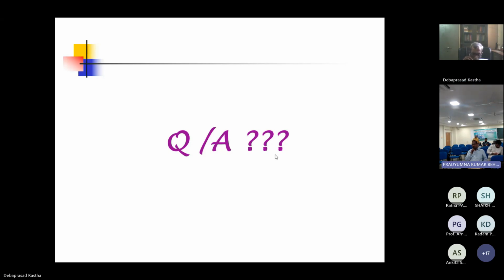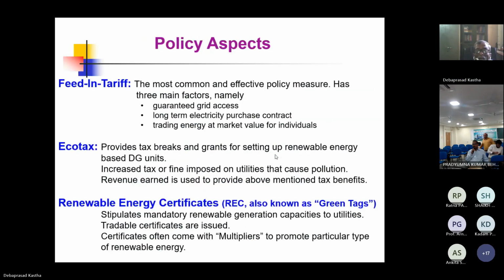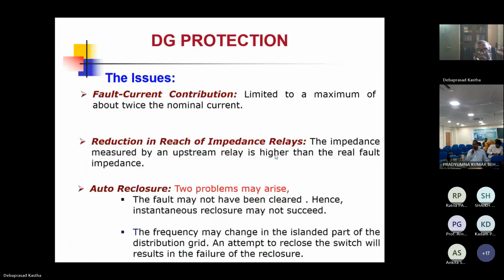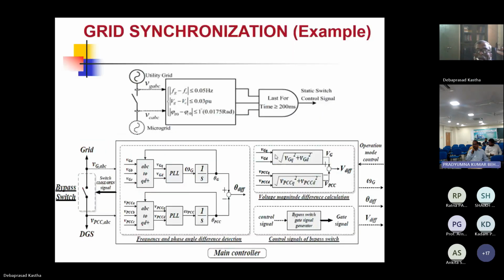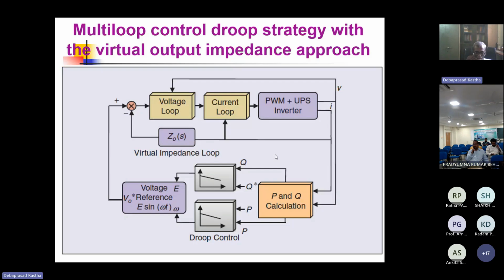Regarding that virtual impedance control, can you please explain a bit more? Let me go back to that slide. This is the one you are talking about. So what is it? The voltage control loop, current control loop, and then the inverter. You are sensing the current, and then you are assuming that as if at the output of the inverter there is an impedance Z0S connected. From the PQ calculation with the droop control, you are getting certain voltage reference. But then from there, you are subtracting that I0 into Z0S, so that it is acting like a source with an impedance of Z0S, although actually there is no impedance. The voltage is dropped like that.